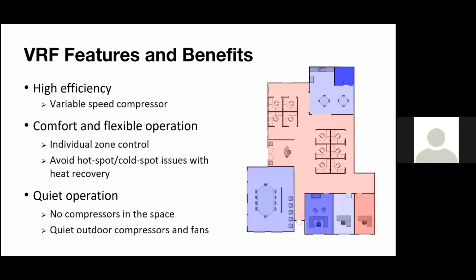So a bit more about the benefits. I'm not going to talk too much about the high efficiency aspect. I already touched on it a little bit, and Jason will get into it in a bit more detail. So comfort and flexible operation. One of the things to remember with VRF systems is that these are zoning systems that are meant to have multiple indoor units serving different zones, which is great for buildings that have various zones that might need heating, while others might need cooling. You might get an internal boardroom that might need cooling in the middle of winter, and then you'll have maybe exterior offices that would need heating. So VRF again is meant to zone your building, unlike a standard single zone rooftop with just one thermostat in your space. So there's lots of flexibility with that.